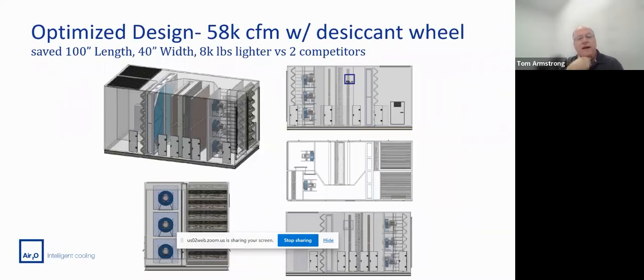But we can also do some very, very highly optimized designs. And that's where Mo's team, their strength in the engineering, the depth of expertise we can bring, adds to our ability. In this case, we really optimized the two tunnels. You can see they're uneven air tunnels. And we have in-house CFD capability. So we were able to do a very precise design on this and do a CFD model to determine whether it was going to be okay in terms of the pressure drops on that side that we were robbing a little bit of space from.